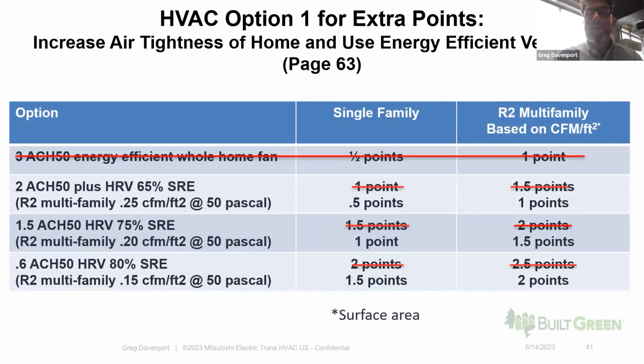In terms of ventilation, there are still energy efficient ventilation credits available under the new Washington State Energy Code. A lot of builders had been doing the whole home fan with 3 ACH 50. That was pretty easy to hit. That credit's going away. Under the new code, if you want to get ventilation energy credits, you can see there's kind of 3 tiers remaining here. 2 ACH 50 is pretty tricky. That's an ambitious goal for a lot of builders with an HRV. I'm not sure if builders will keep doing that. I think most builders will just do heat pumps for space conditioning, heat pumps for hot water, and be good to go.